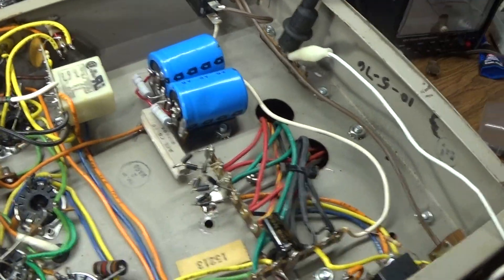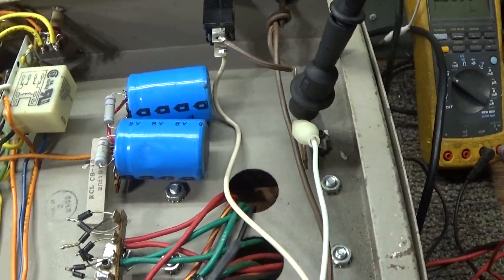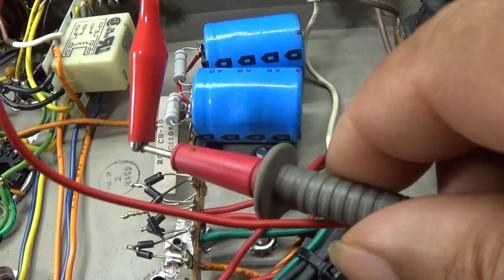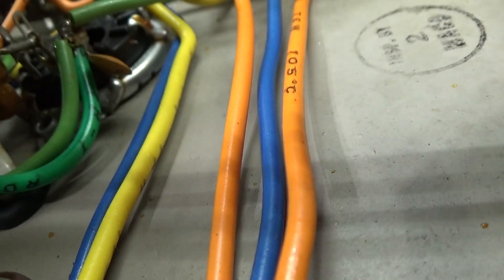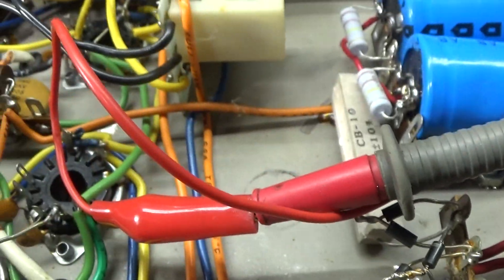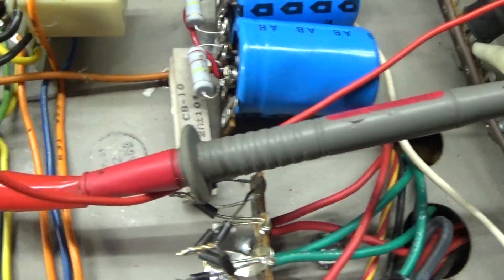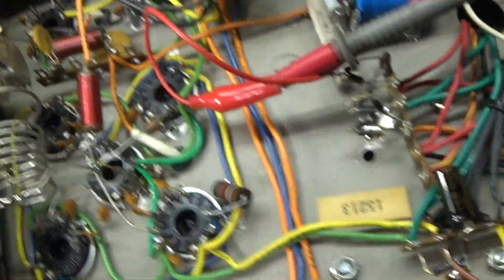You can test the voltage on the caps with your meter. I used to hook up jumpers like that, but as I got older and a little smarter, nowadays when we put a jumper we do it like this. That way there's no exposed metal when I'm hooking the jumper to the test lead.